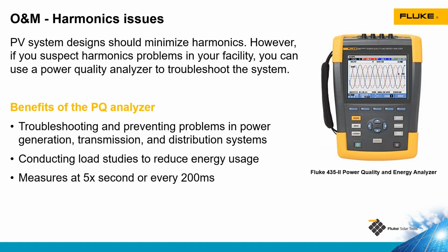An interesting thing about certain power quality meters is they're able to do load studies. So we can measure power and energy consumed by a load over time. Then we can take that information and use it to properly size an energy storage system for backup resiliency purposes. So it's a good tool for that if we're doing battery-based systems that are used for backup purposes.